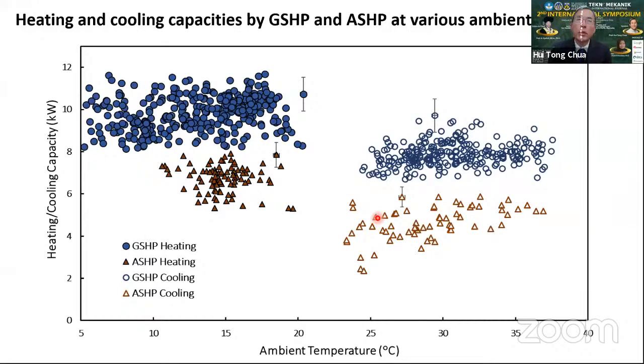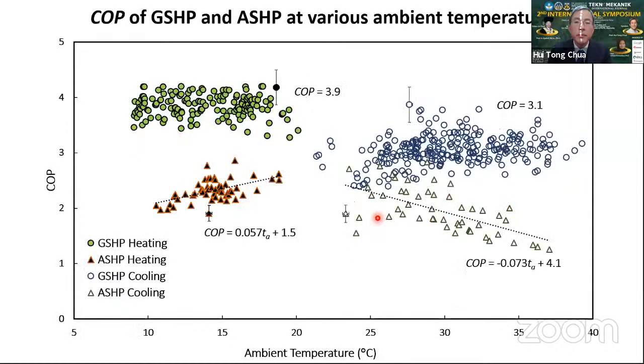Very importantly, these data are collected over 2 years, so it spans across 2 summers and certainly 2 winters. Because of the disparate absolute capacities, both in cooling and heating, we analyze the data based on the coefficient of performance of the air conditioning unit. Simply put, the coefficient of performance means the efficiency of the system, and it is a ratio of the heating or cooling capacity derived by the machine divided by the electrical power input into the machine. Importantly, in terms of the COP auditing, the ground source heat pump actively considers the power consumed by the submersible pump, which consumes 900 watts.